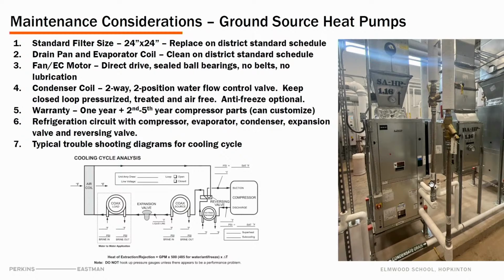There's a control valve that restricts that water flow. It's important that we keep that closed loop pressurized, keep it treated, and keep it air free, like we would any other closed loop. We have seen on ground source systems that the ground loop does need to be treated like any other loop would. We have seen some bacteria build up in ground source heat pump loops that just has to be treated, but that's all done through the monitoring process to make sure that doesn't get out of control.